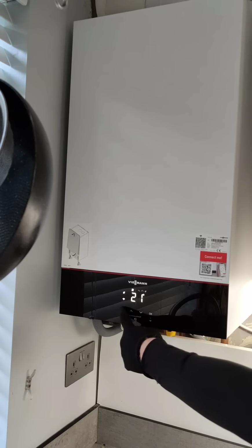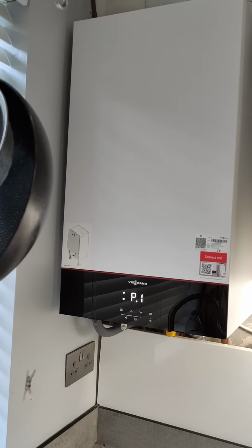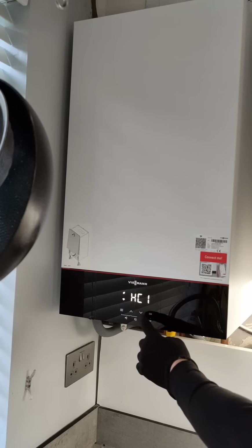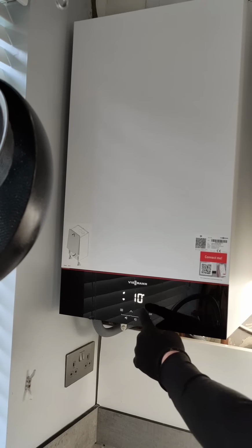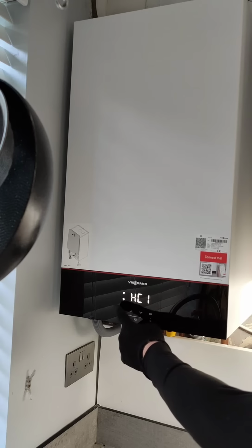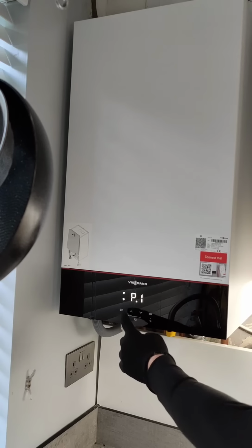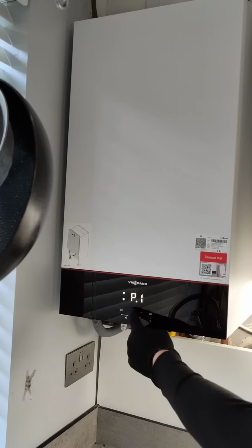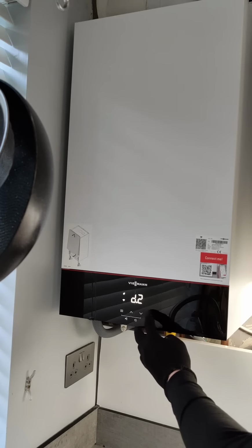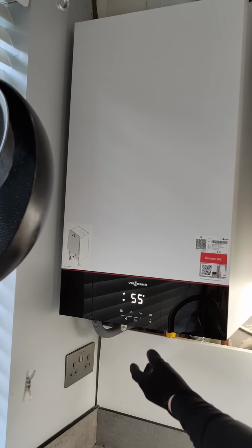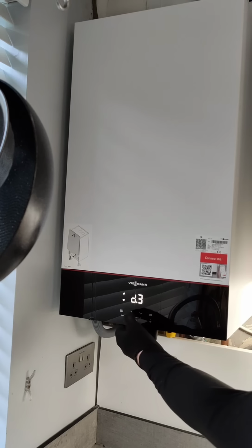If we hold the menu button for 4 seconds, we'll bring up the P menus. Now P1, what we've got here is heating circuit 1. This is the nighttime temperature and the daytime temperature. P2, you can bring up all the information menus. So D1 is the outdoor sensor temperature. D2 is the flow temperature. D3 is the pump speed in percent. So the pump's off, so it's at 0%.